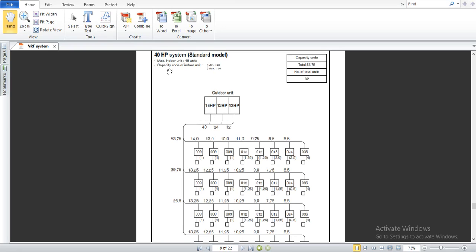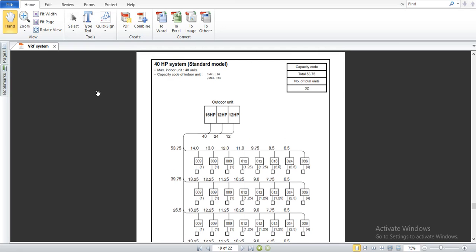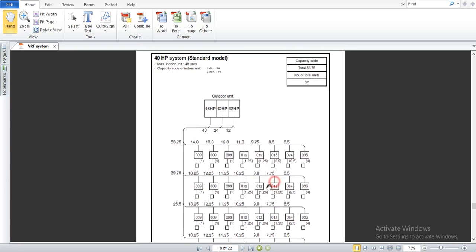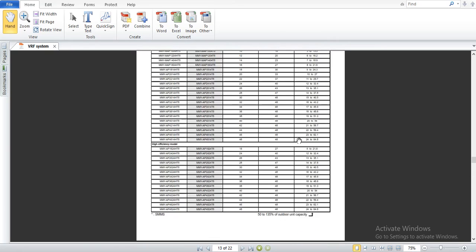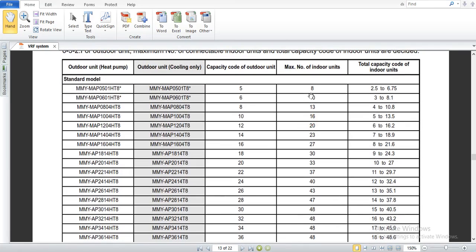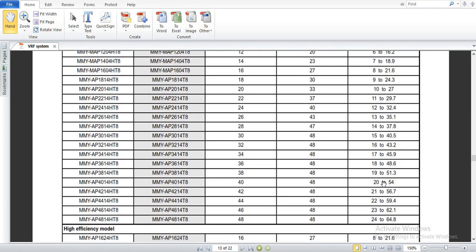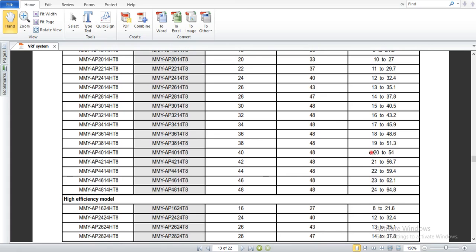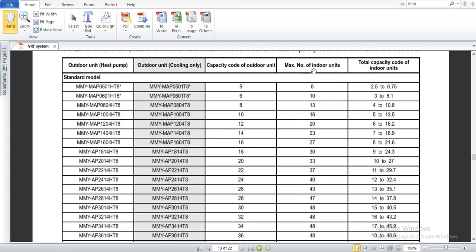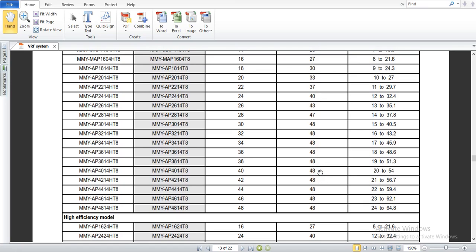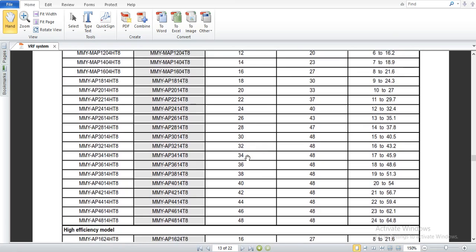Now we select the outdoor unit based on 32 indoor units and a capacity code of 53.75. Going back to the combined outdoor unit model table: 53.75 lies between 20 and 54, so we select that row. The maximum number of connectable indoor units is 48, and we have 32 in our project — we are good with both factors. So we can select this 40 horsepower outdoor unit for our system. If heating is required, we select the heat pump model; if cooling only, we select the cooling only model.